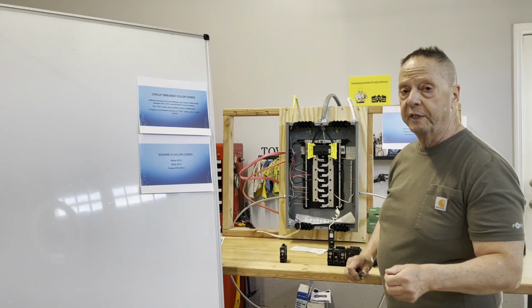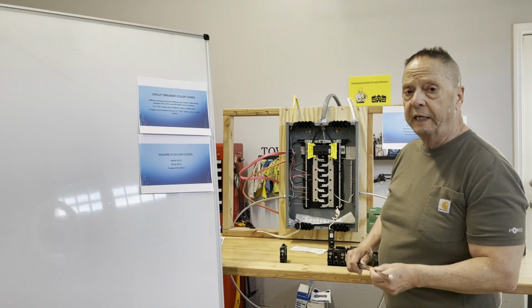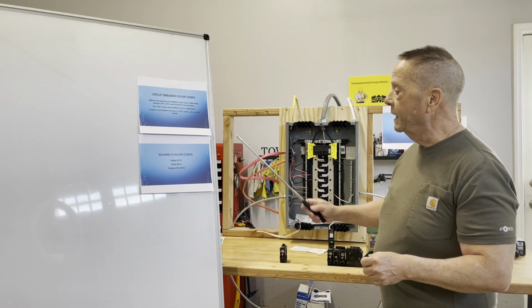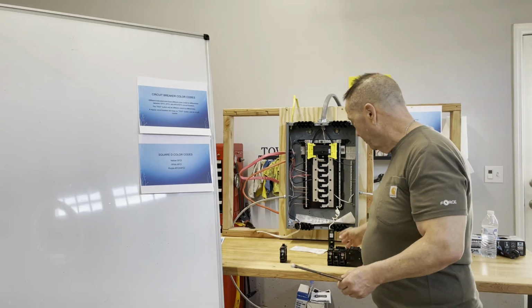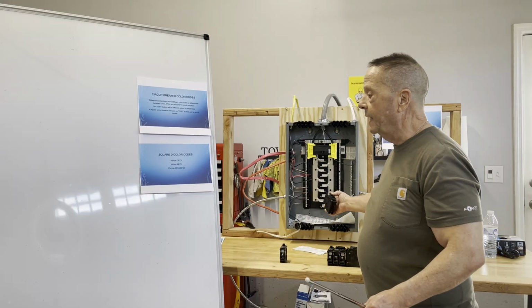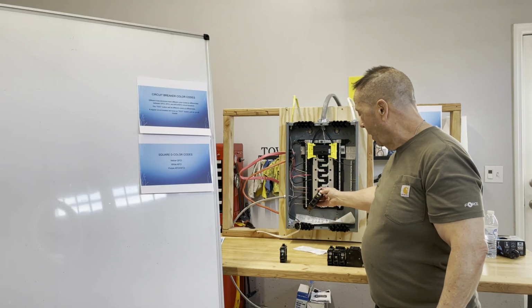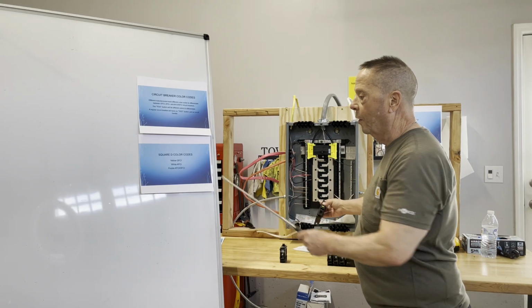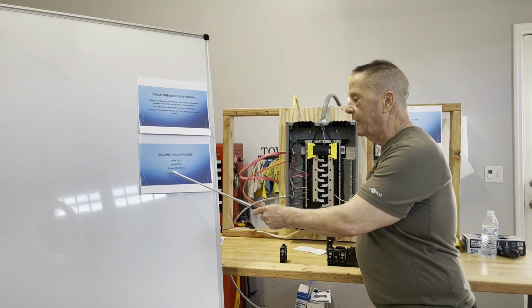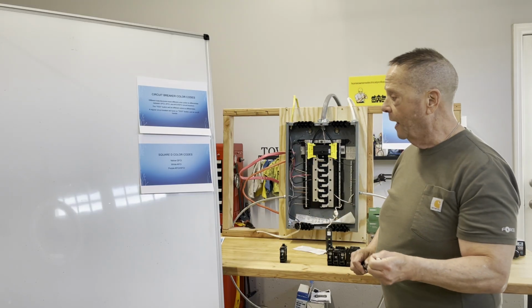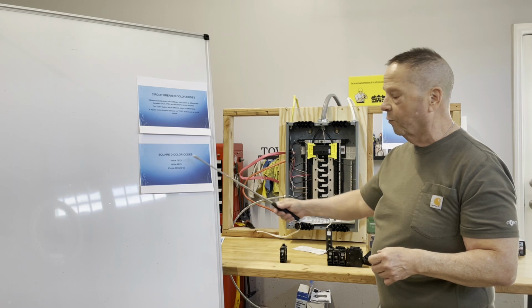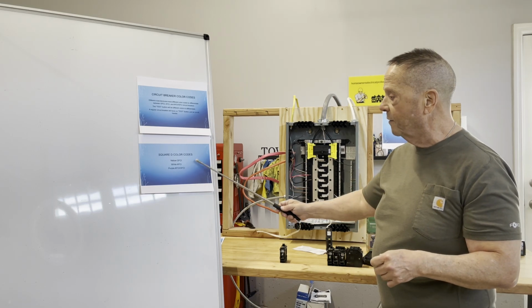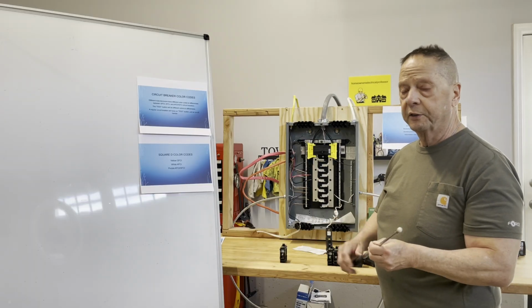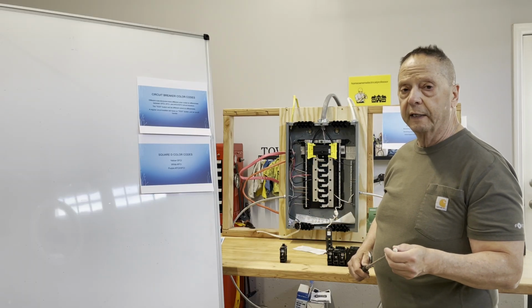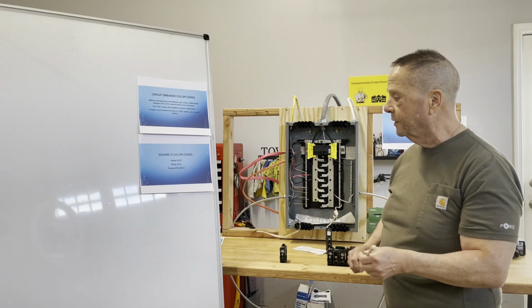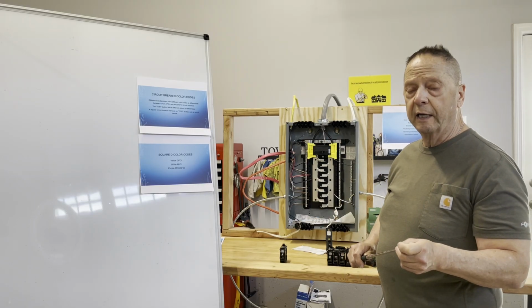Other manufacturers have a different color code, ITE, General Electric, Eaton, those brands. But anyway, if you have a Square D panel and you see a little yellow test button on here, that means it's a ground fault receptacle. If this button were to be white, it would be an arc fault. If it's purple, it's a combination. It protects against arc faults and ground faults. I have a set of videos on what a ground fault is. You can look that up. I also have a video on what an arc fault is. Remember, a ground fault protects people and animals against getting shocked, whereas an arc fault helps prevent fires.